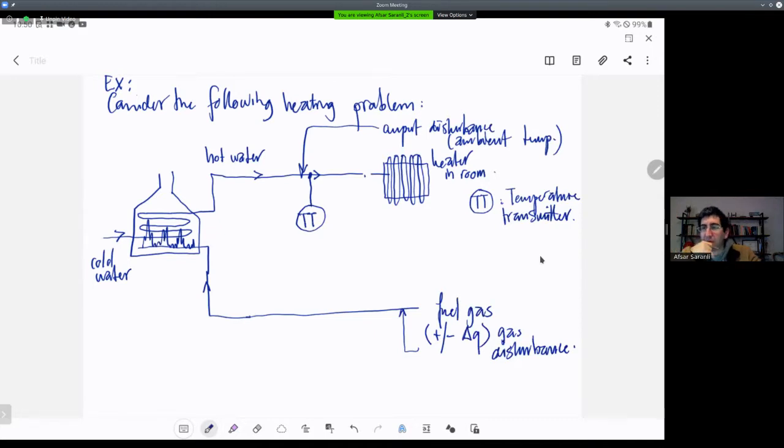It's like your Honeywell control system in the laboratory, right? Usually the measurement devices are standalone. They make the measurement, they digitize the measurement. They make the measurement, either they digitize it and send it over a network connection, or they are analog current-based, let's say, transmitters that just send a current, a constant current related with the temperature along a line to the measurement device or the digitization device. Okay, so this is like our sensor, and we also have a temperature controller.